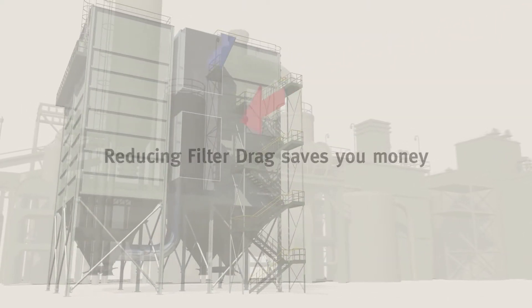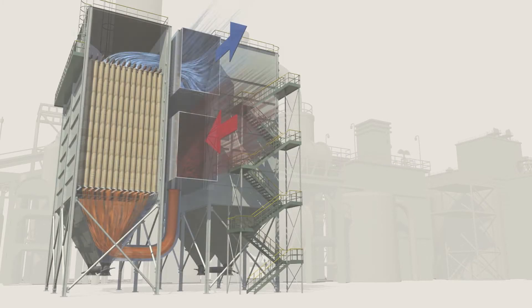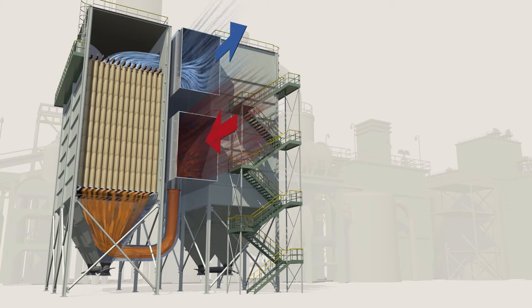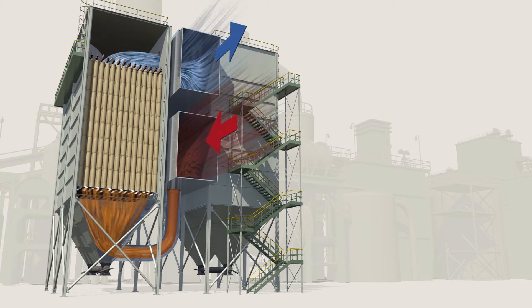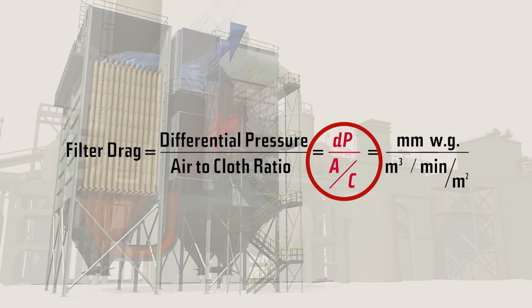Filter drag. Reducing it saves you money. By definition, it is the total resistance to the airflow in your bag house caused by the combination of the filter media and the dust on or in the filter media. Higher resistance results in lower operating efficiency and higher costs for your bag house. This formula breaks it down: filter drag equals differential pressure divided by air to cloth ratio. Simply put, it is the amount of force or energy it takes to move air through the bag house.